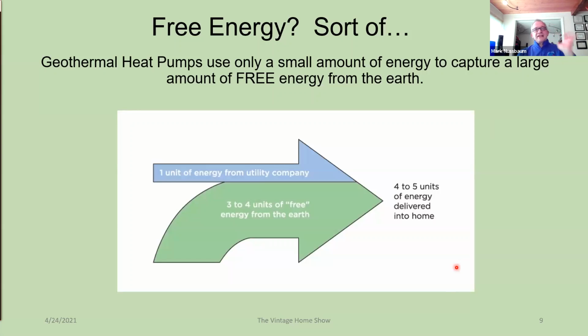Some people say geo has free energy. Well, it does, but you've got to spend some energy to capture that energy. So a geo system has a coefficient of performance of about 4 to 5, depending on the equipment you buy. That means for every unit of energy I put in to run the fan, the compressor, and the pumps, I get 3 to 4 units of energy out of the ground that's delivered to the house. Those two are added together to deliver to the house. Air source heat pumps are the same thing. It's just that this bottom component is derived from the air, and it's not as much. They're not quite as efficient, maybe 2 to 3 versus 3 to 4 on that.